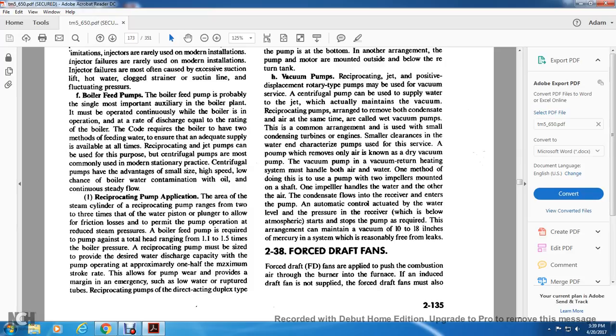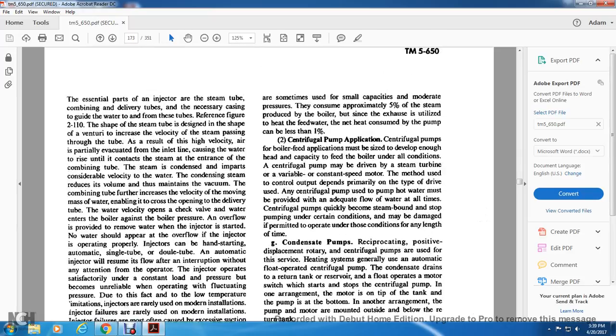Reciprocating pumps of the direct acting duplex type are sometimes used in small capacity, moderate pressure plants. They consume approximately 5% of the steam produced by the boiler, but since the exhaust is utilized to heat the feed water, the net steam consumption of the pump can be less than 1%.